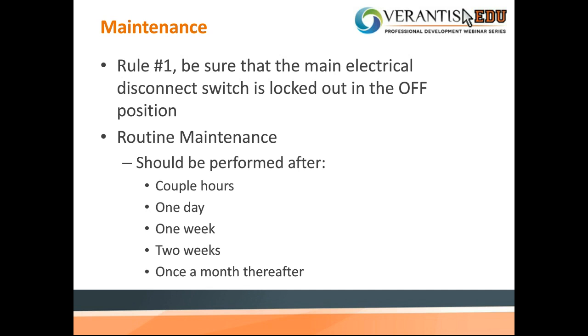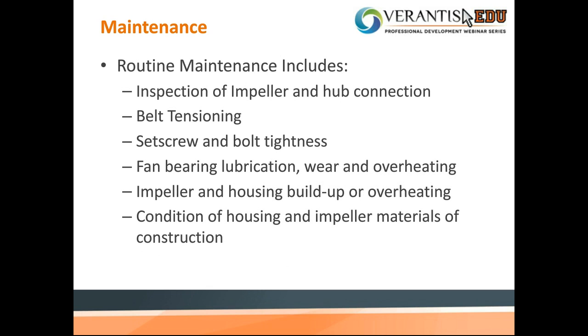The routine maintenance includes inspection of impeller and hub connections, belt tensioning, set screw and bolt tightness, fan bearing lubrication, wear and overheating, impeller and housing buildup or overheating, and condition of housing and impeller materials of construction.